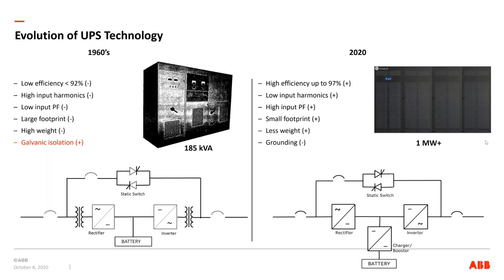There's no galvanic isolation. If there's a ground fault on the battery, the breakers will trip, fuses will blow, and the UPS will transfer to static bypass and continue to feed the load that way, but it cannot operate in its normal mode. The possible option to get back to handling that failure mode is if the UPS is installed in what's known as a high resistance grounding environment, which essentially means that instead of a solid grounded system, the system is grounded via a resistor that limits the fault current in case of a ground fault, typically to around 5 amps. If there's a ground fault, nothing will trip, nothing will shut down, the UPS and everything will continue to operate. There's ground current, but it is limited by the resistor.